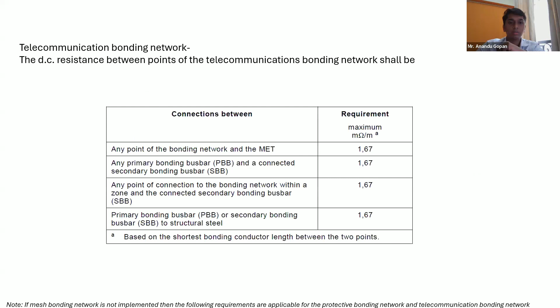So in a telecommunication bonding network, you will have a PBB, which is this thing, and you will have your SBB, the secondary bonding bus bar. You will have your primary bonding bus bar, and an interconnection between the primary and secondary bonding bus bars, which will be interconnected within that zone.